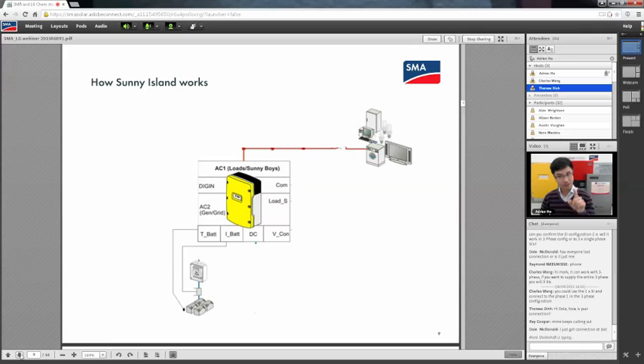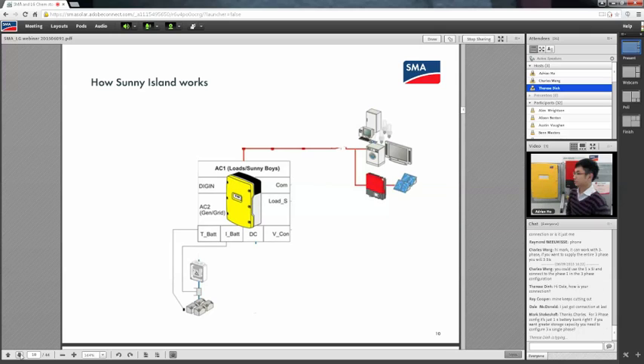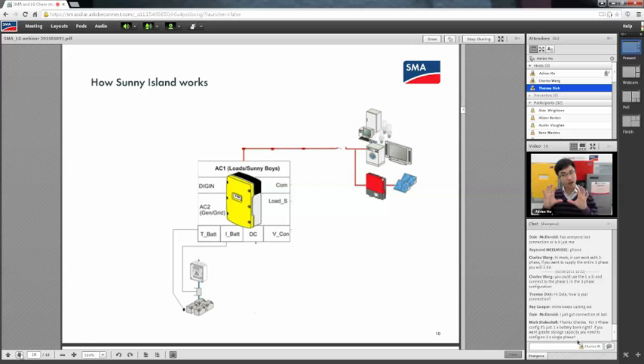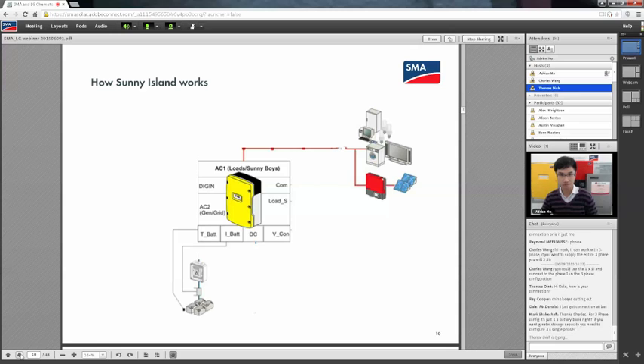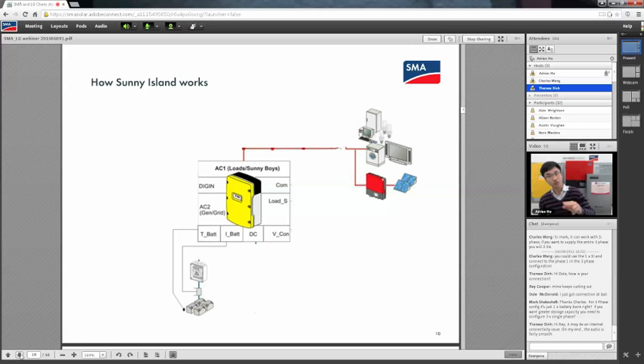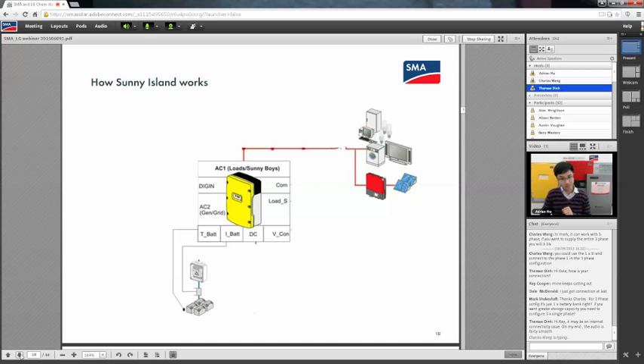But as always, there is only consumption in this diagram. You need some form of generation to recharge the battery. So now I've got the Sunny Boy. A Sunny Boy 5 or 4 kilowatts now attaches to the system. All those string inverters are called grid-connect inverters, and they now see this Sunny Island electricity grid, so they can generate power from the sun. During daytime, the solar would supply the loads directly. Excess energy would then feed through the Sunny Island back into the battery. And of course, at nighttime, everything is supplied by the battery. The system works perfectly this way if the loads and the generation are all sized well.